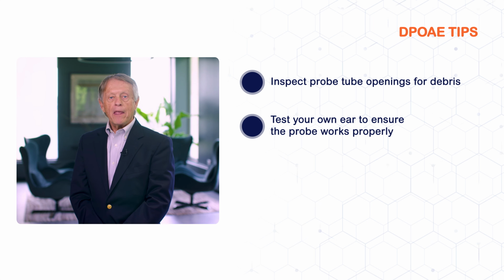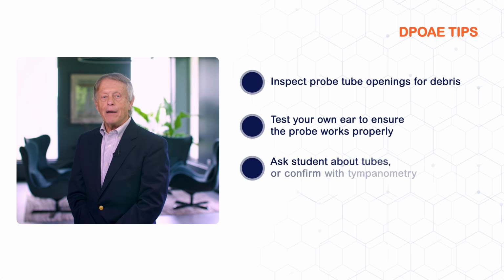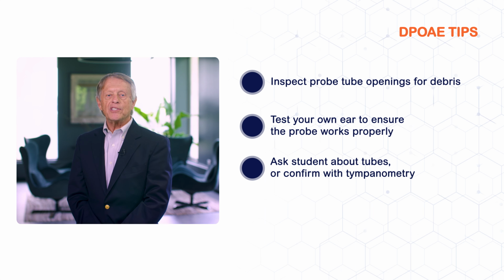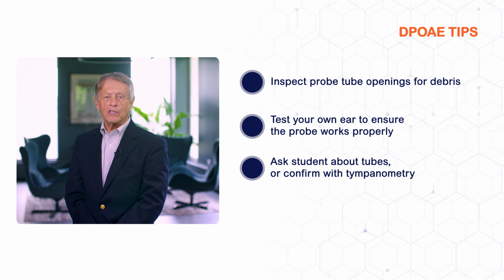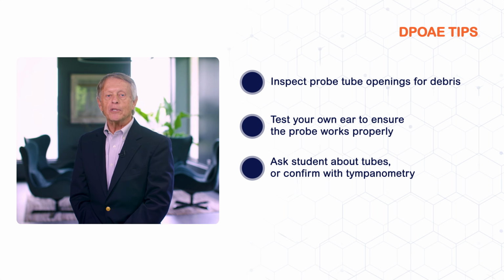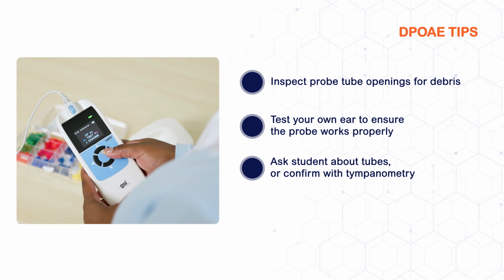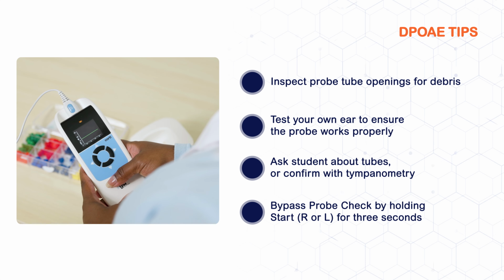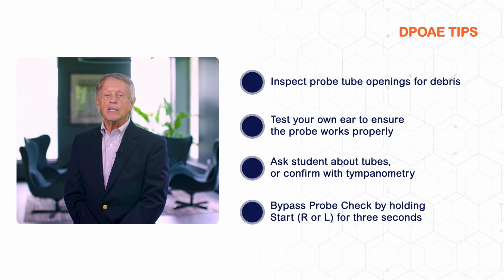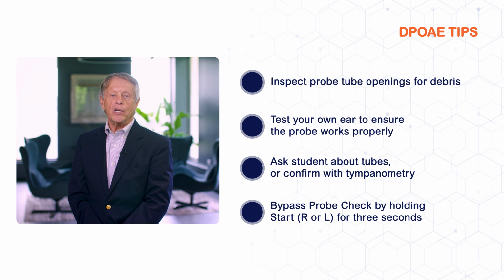Another tip: if you have a student's ear that cannot pass the probe check, ask him if he has tubes in his ears, or confirm this with tympanometry. If there's a student with tubes, the probe check can be bypassed by pressing and holding the start button, R or L, for 3 seconds. When the button is released, an in-ear sound calibration will occur and the test will begin.